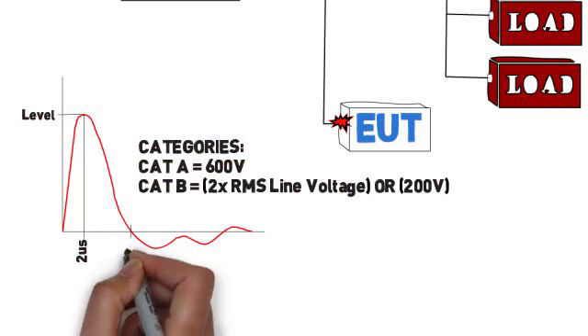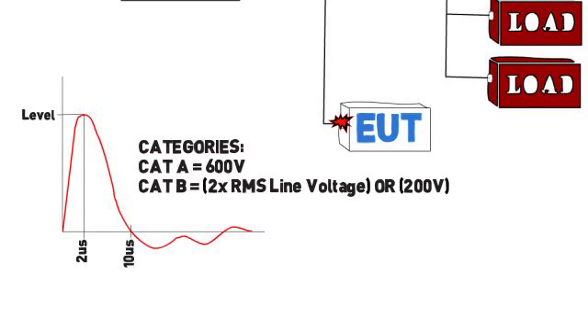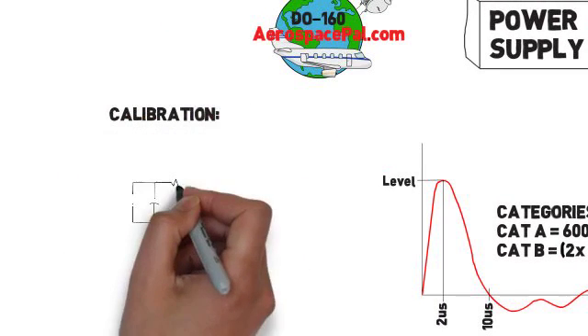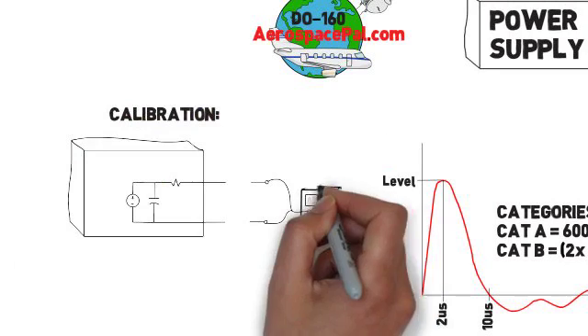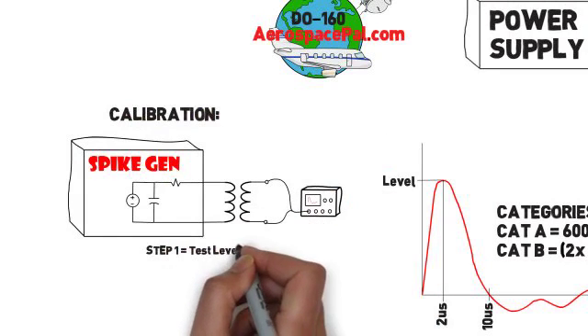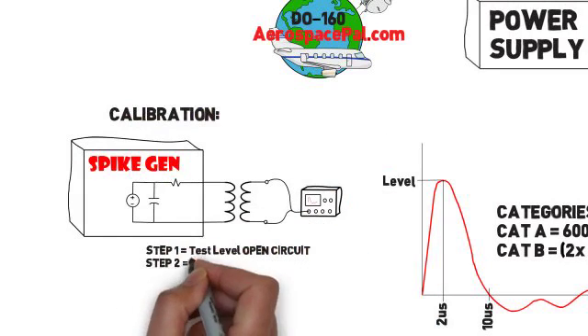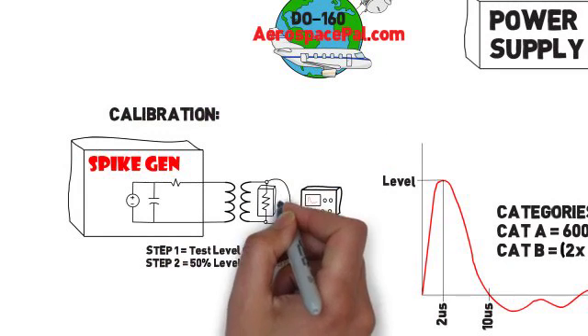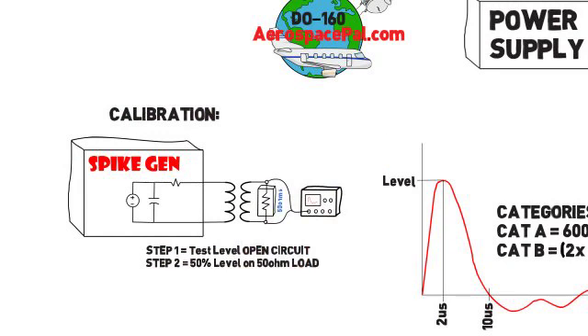The calibration for this test is pretty simple. Use the voltage spike generator to achieve the category level by injecting on open circuit. Then inject on a 50 ohm dummy load to achieve 50% of the category level. This ensures the generator has a source impedance of around 50 ohms.